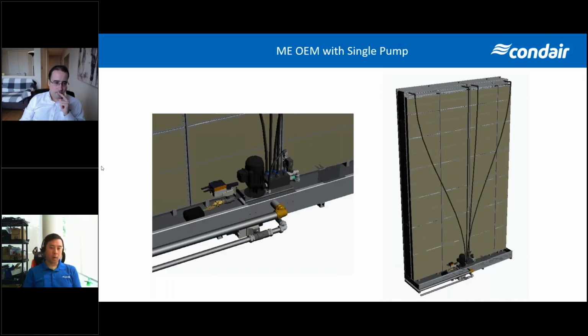So one, of course, is what we call an OEM unit. This is more similar to your traditional evaporative cooler or swamp cooler. But in this case, the requirements are, we have a third-party controls contractor, we have a set control scheme that we need to operate to. We do not want to use the Condair integrated controller with all of our logic in terms of controlling the individual components, the water management, the hygiene. They just want the evaporative module with all the components that they can control based on their control scheme.